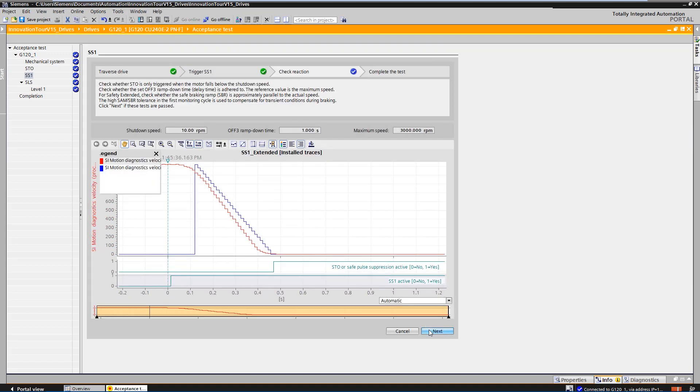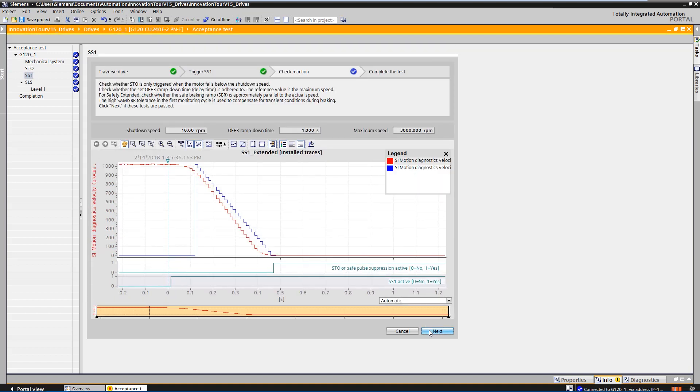The acceptance test automatically created a trace with the most important parameters. The trace can be used to check that the drive is decelerating in accordance with the specifications and that the state of the safety signals is correct. During the braking process, safe stop 1 was active and after ramping down, the drive changed to safe torque off.